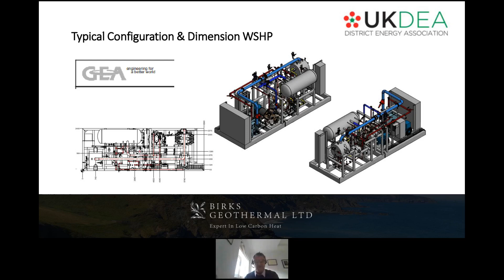And of course, we believe that water source heat pumps generally do have a higher coefficient of performance than air source heat pumps. And so over a longer time frame, the economics can start to favour water source over air source. But a water source heat pump, or in the case of groundwater fed heat networks, has to be connected to a well field where the groundwater is harvested. And that well field is a considerable capex consideration.